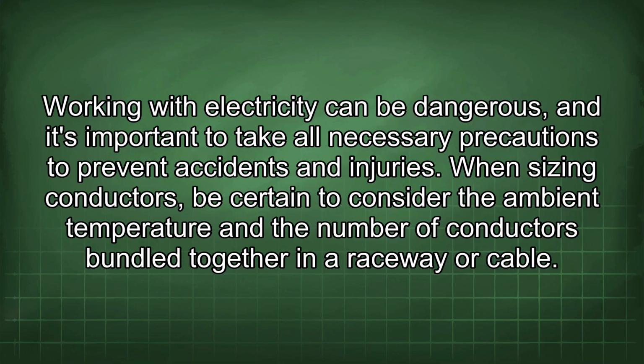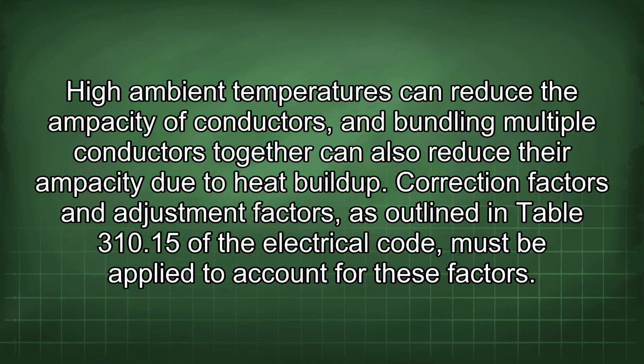When sizing conductors, be certain to consider the ambient temperature and the number of conductors bundled together in a raceway or cable. High ambient temperatures can reduce the ampacity of conductors, and bundling multiple conductors together can also reduce their ampacity due to heat buildup. Correction factors and adjustment factors, as outlined in Table 310.15 of the Electrical Code, must be applied to account for these factors.